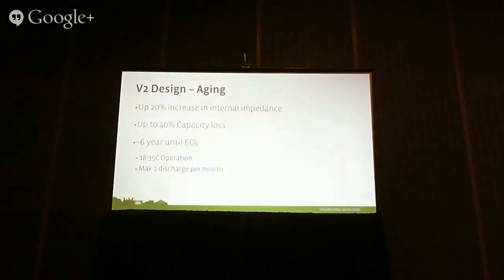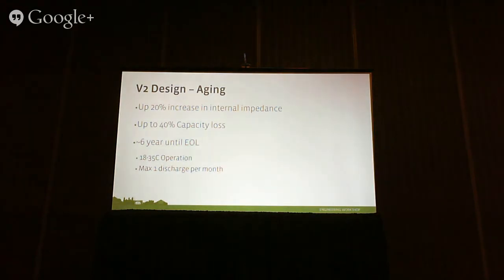So, aging. We designed the module for a 6-year life operation, 6 years until end of life, and we designed that for our use case. This will be very different in different use cases, so special attention must be paid to that. Our use case is 18 to 35C in our data center, and a maximum of one discharge per month, which we get from statistical data on how often we actually see outages in the data center and how quickly it returns.